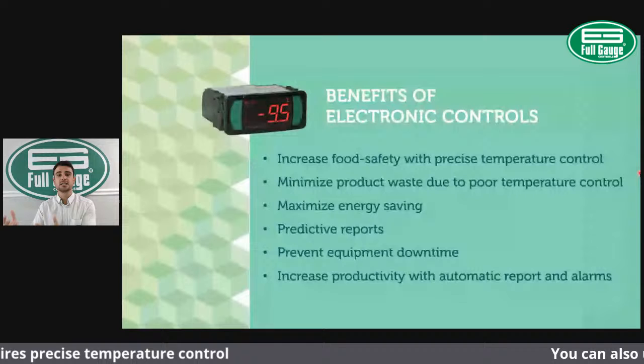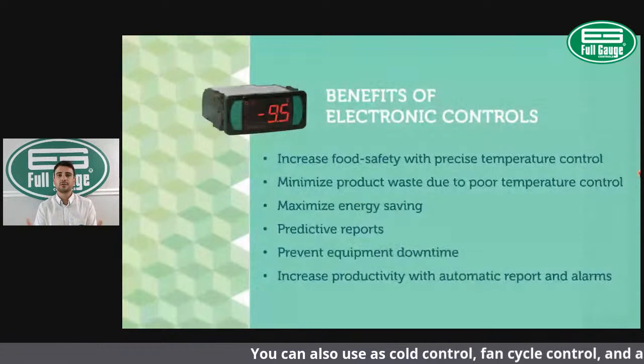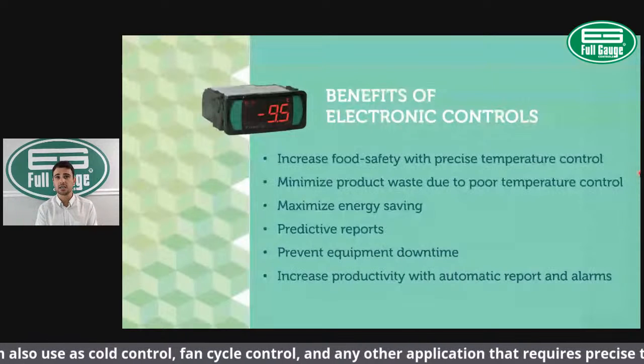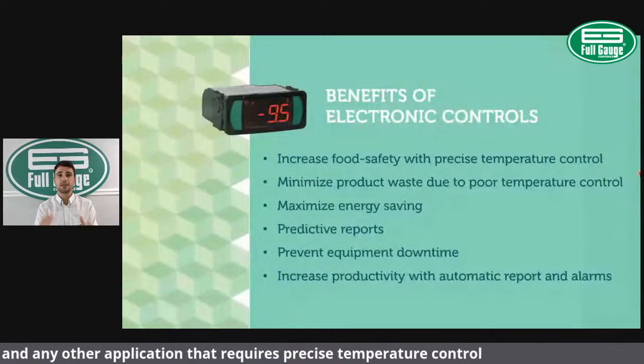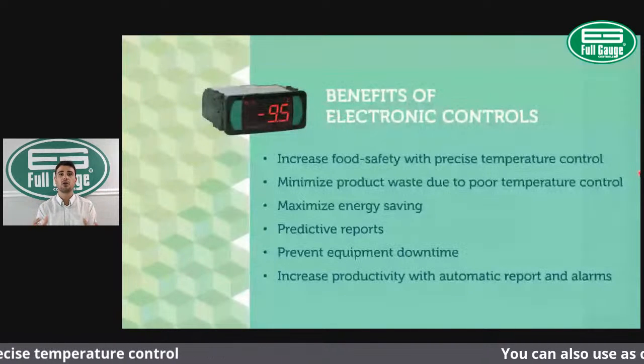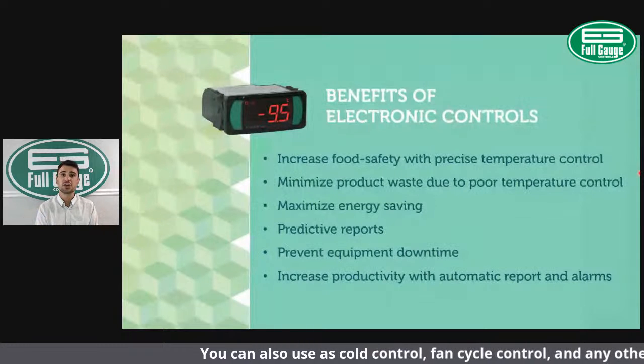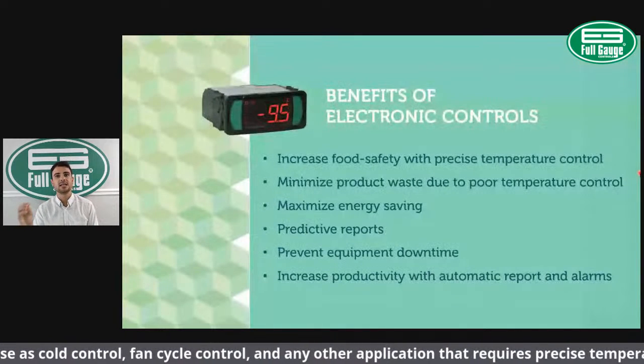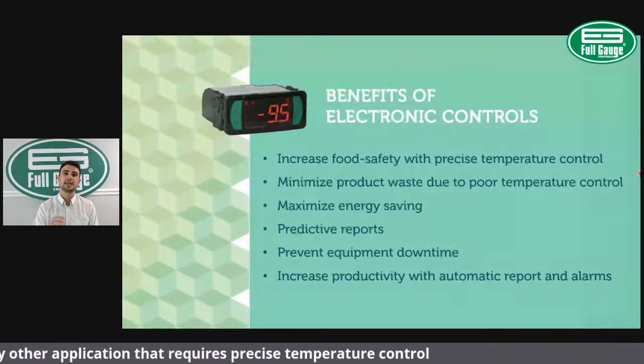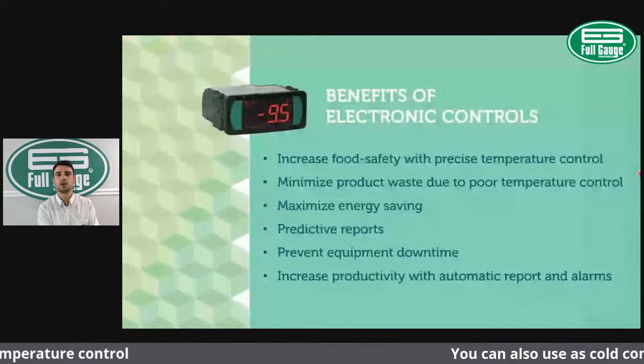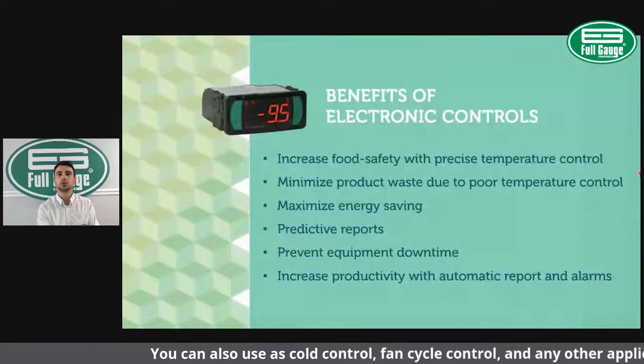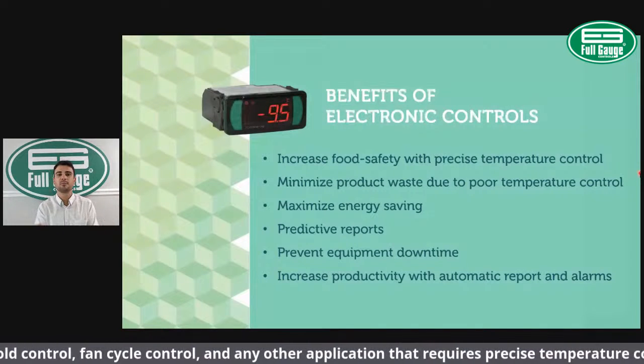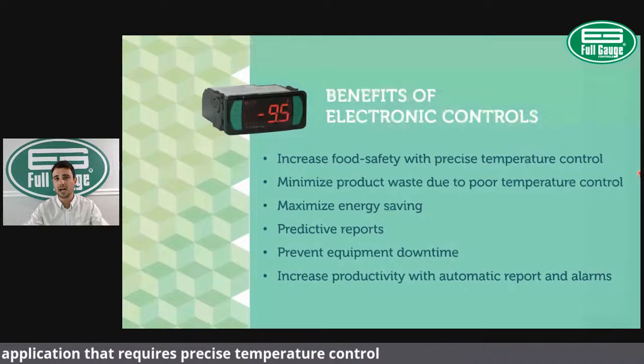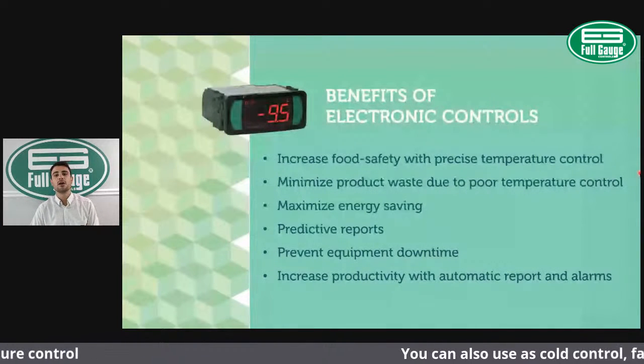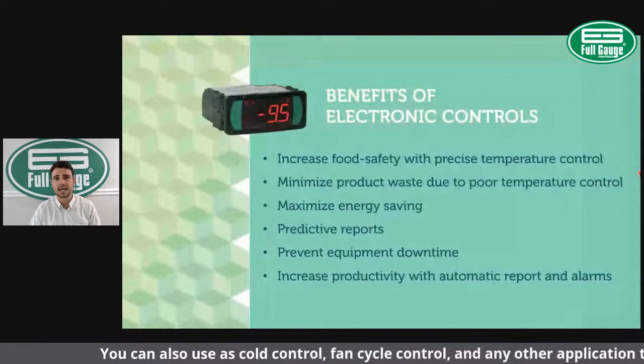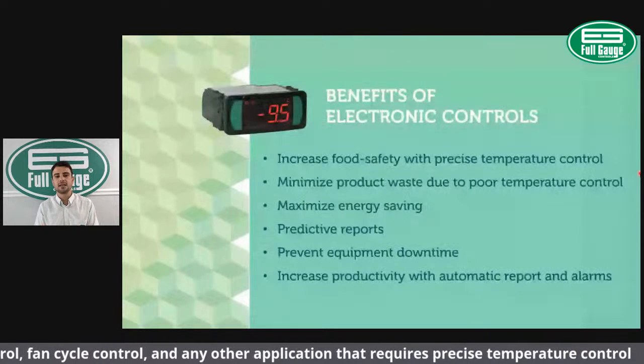In addition to that, you minimize product waste due to poor temperature control. We all see there are some very temperature-sensitive products. If you go outside of that desired or acceptable temperature range, you're risking losing products. Ice cream is a good example of that. Once ice cream melts, it doesn't get back to its original quality, so it becomes a poor quality product due to poor temperature control. By having precise temperature control, you can extend shelf life for your products and maximize energy saving with better on and off cycles, with more efficient defrost and things like that.